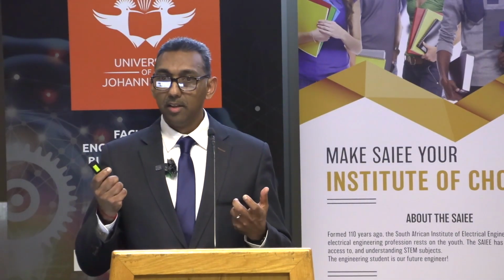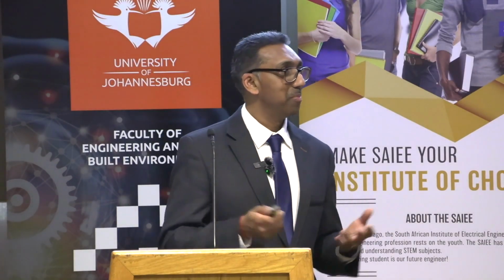What we were picking up was high failure rates on moving parts, things like breakers, switches, bearings, braking systems, and the guide vanes that regulate the water. We were seeing unusual failures coming through. We had to adjust how we do maintenance, adjust how we do fault finding, and replace equipment. Mechanical equipment nowadays is designed for purpose, not for longevity like before, so we have to reevaluate what we put in and how we put it in. That has been a major challenge for us.